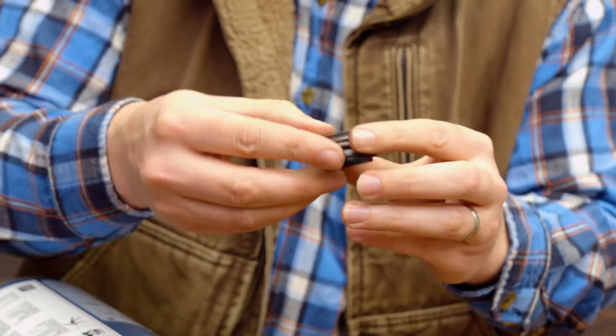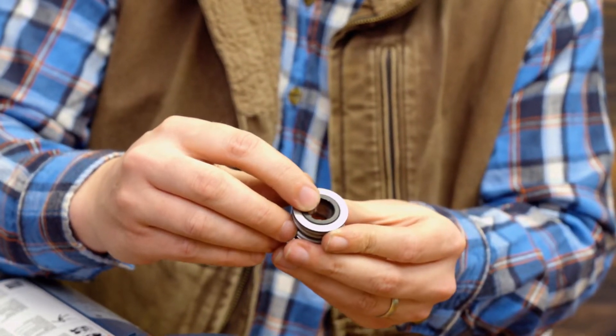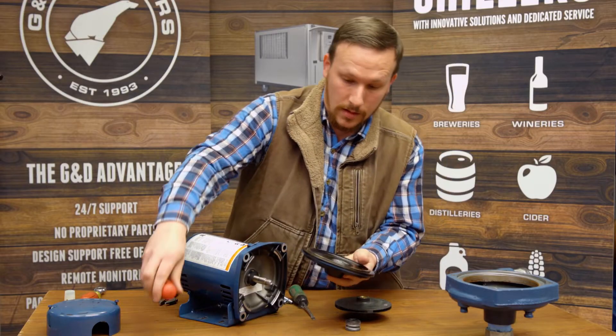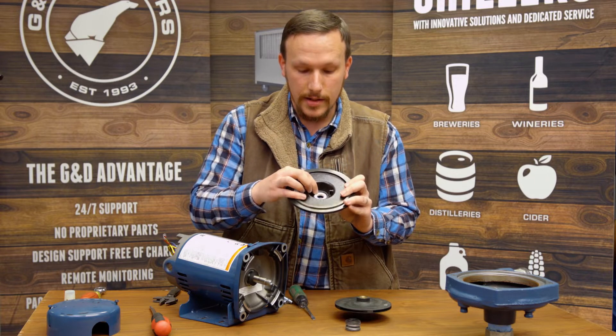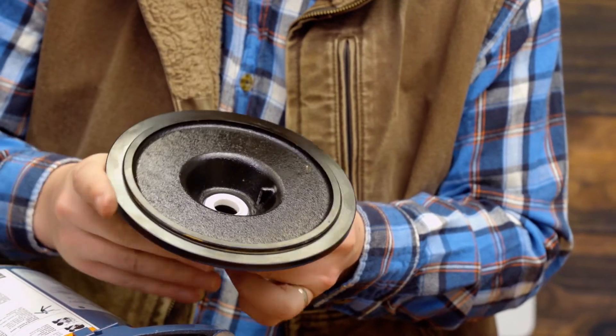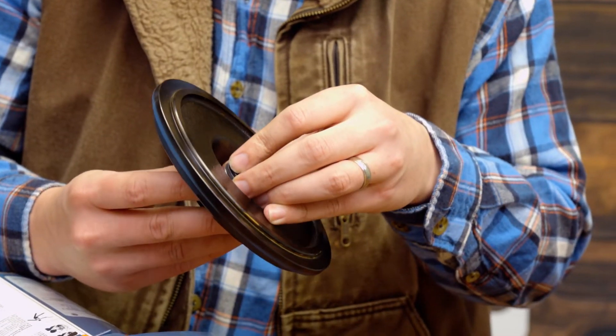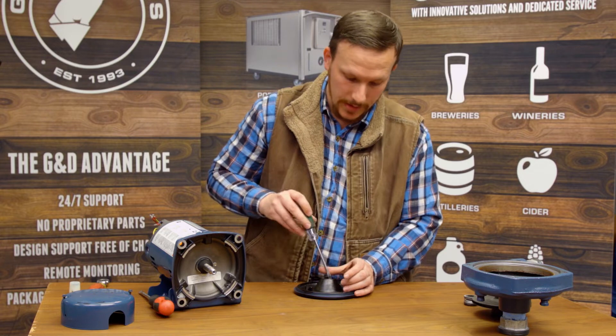The next step is to unthread the impeller from the shaft. Sometimes it breaks free really easily, other times it might take a little effort — and it is a right-handed thread. Now we should be able to remove the shaft seal from the shaft itself. You want to use two screwdrivers to do that; you don't want to pry unevenly and end up damaging the shaft or the seal plate.